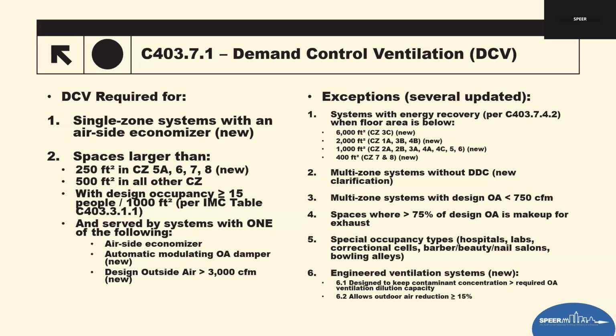Plan reviewer tips: identify any space that's greater than 250 or 500 square feet with more than or equal to 15 occupants per 1,000 square feet. Then that's when these things will kick in and be triggered. Check whether the system has an economizer modulating outdoor air damper or an outdoor air greater than 3,000 CFM. And then verify DDC capability for multiple zone systems. Lastly, confirm exception documents for energy recoveries or engineered ventilation have been documented clearly, and they're taking those exceptions.